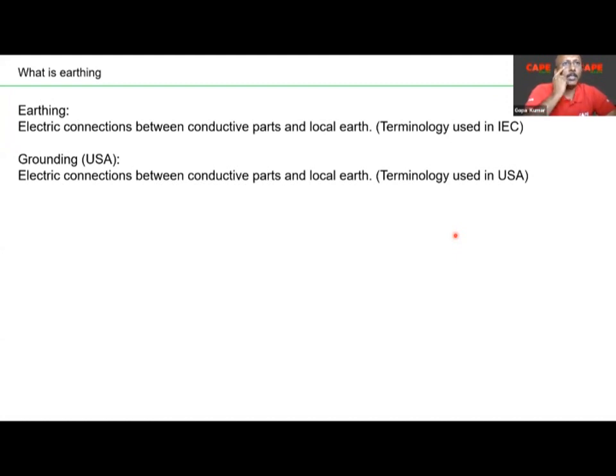That part of the installation is supposed to give an average life of about 40 years. So if we make a very good earthing, of course, the life of the installation will be very good, and the failures or accidents are very much reduced. Then what is the purpose of earthing? The main purpose of earthing is to create a stable voltage of the power supply with respect to earth.